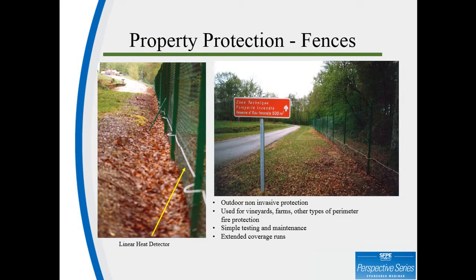This is a picture of a vineyard in France where the detector is used strictly as detection. While it's common for the linear detector to be paired with some type of suppression system, there are also plenty of applications where the linear heat detector is the only system component. The goal of the perimeter fire protection is to detect a forest fire and alert the appropriate personnel so they can respond appropriately. Given the linear heat detector is a fixed temperature detector, the seasonal temperature changes are not a factor in this application.